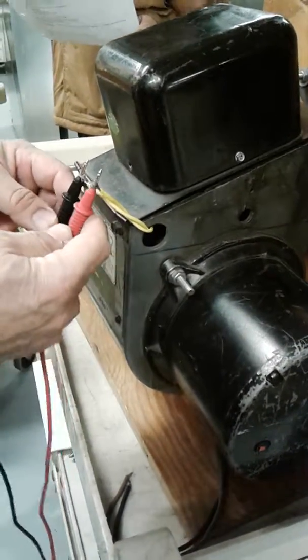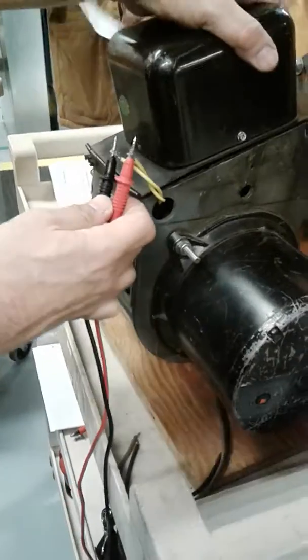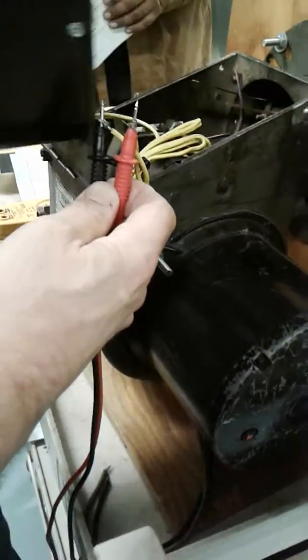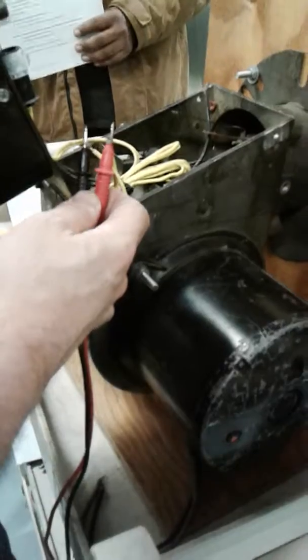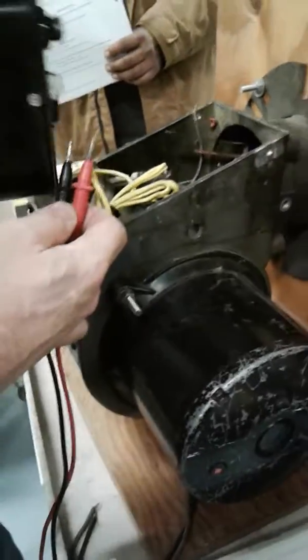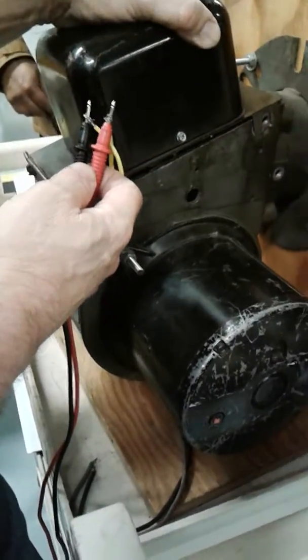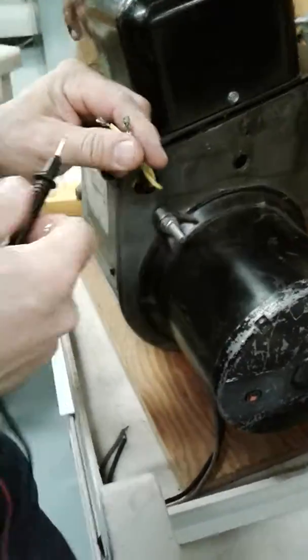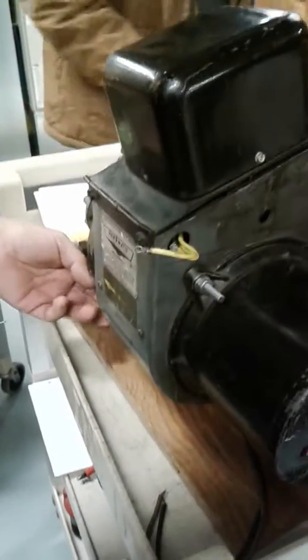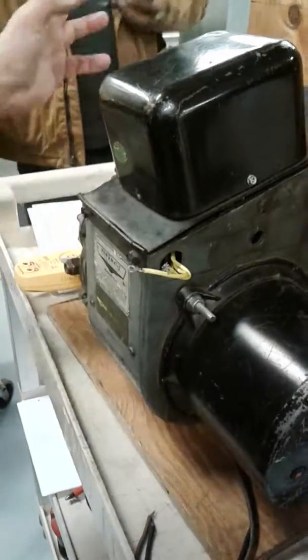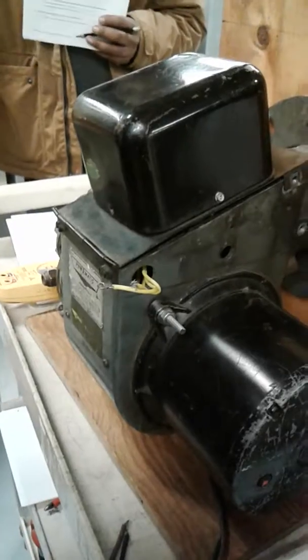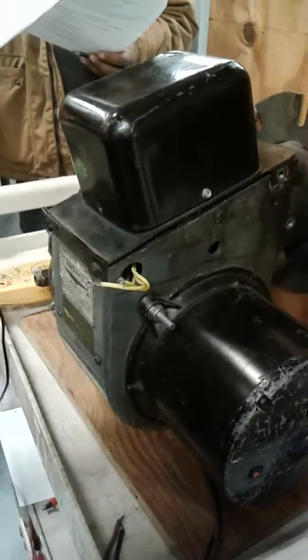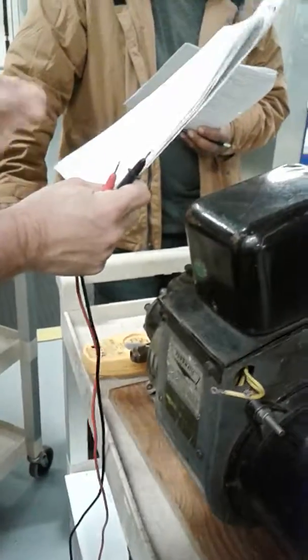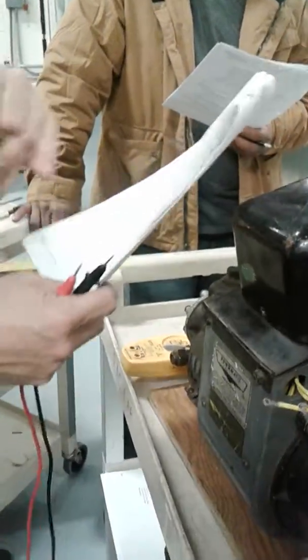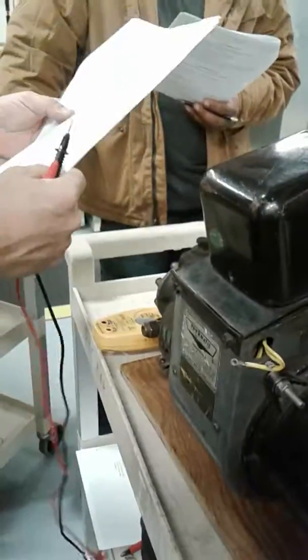Okay? Now, if you really want to see things dramatically change, open it up and you'll see a huge difference in the resistance reading on your meter. I mean, you can physically watch the meter, you'll be like, holy cow. Okay? And it does work. This light that is coming through of this and here doesn't affect that? No. It's just directly this one? Yeah, pretty much right there. You can close those off too. Make sure it's in total darkness. Okay? Alright, so letter D. Check the continuity of the CAD cell. Keep in mind, no flame means total darkness. Okay? Next page is the questions.